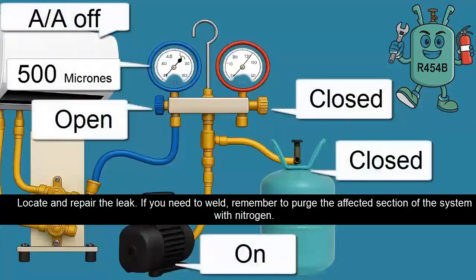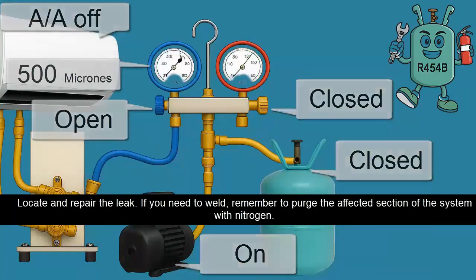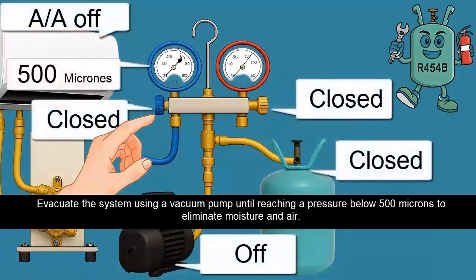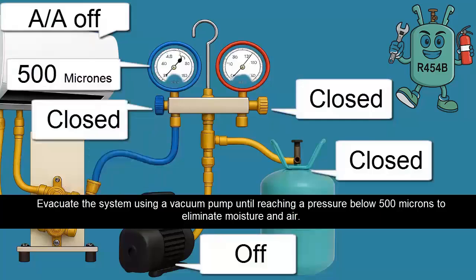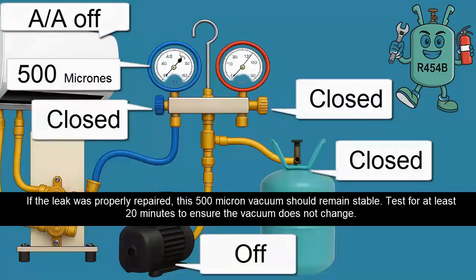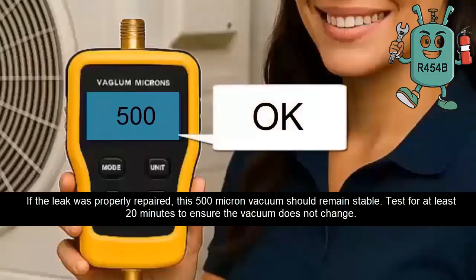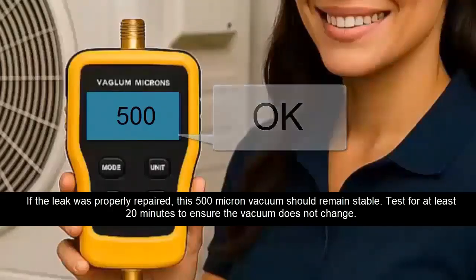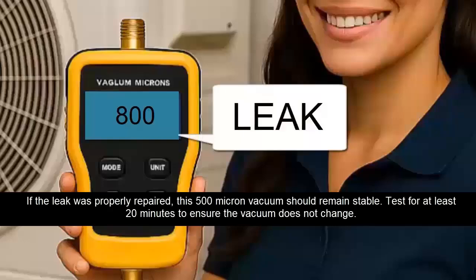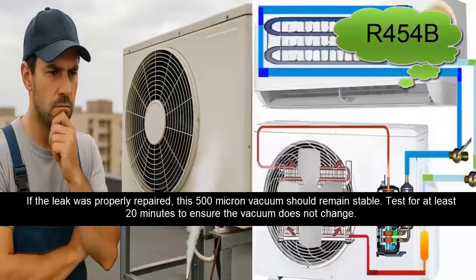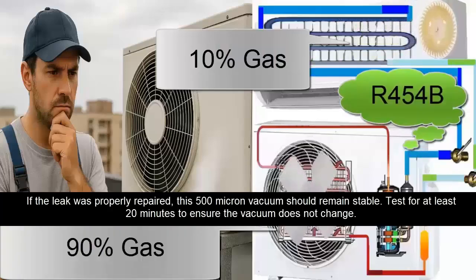Locate and repair the leak. If you need to weld, remember to purge the affected section of the system with nitrogen. Evacuate the system using a vacuum pump until reaching a pressure below 500 microns to eliminate moisture and air. If the leak was properly repaired, this 500 micron vacuum should remain stable. Test for at least 20 minutes to ensure the vacuum does not change.